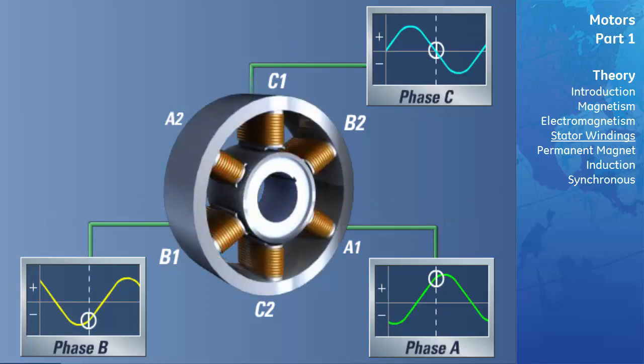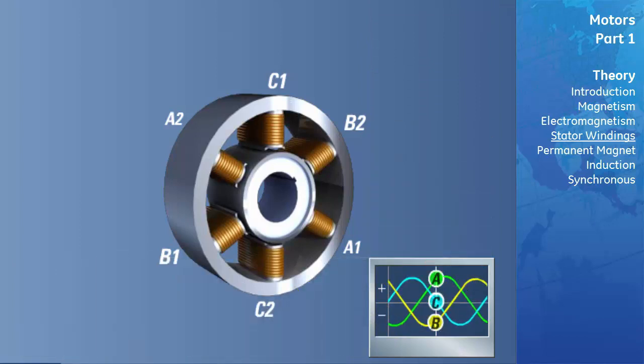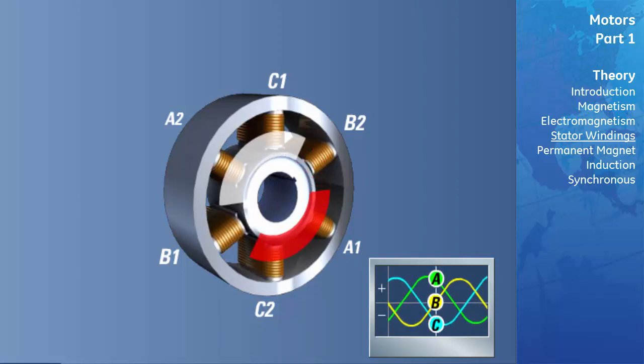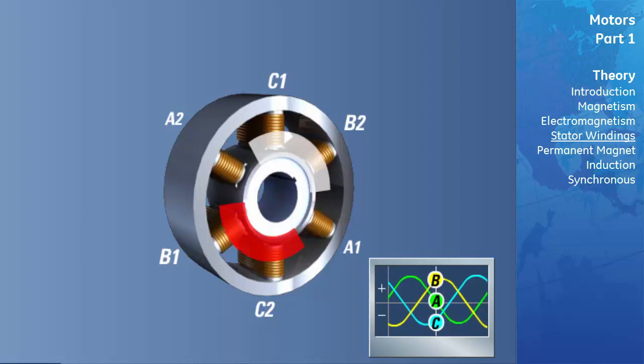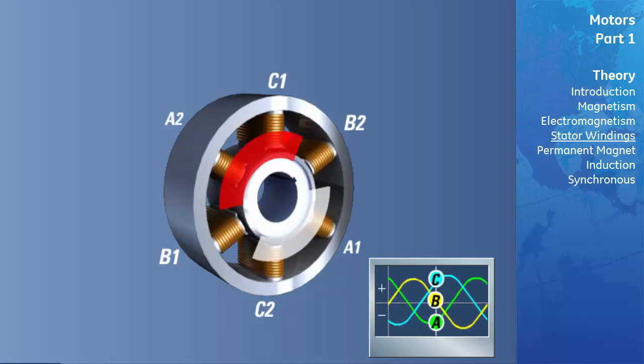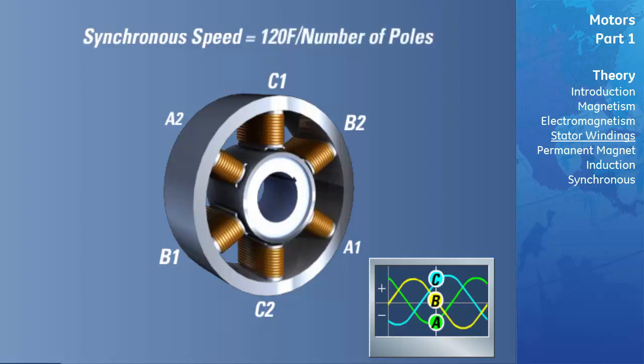If we compare the angular displacement of the field, we can see that it has rotated 60 degrees. If this evaluation is repeated every 60 degrees for the rest of phase A's cycle, we will see that the resultant stator field goes through one complete revolution, or 360 degrees. With a frequency of 60 hertz, this means in one second the field will go through 60 complete rotations, and in one minute, 3600 rotations. The speed of the rotating magnetic field is referred to as the synchronous speed, which can be calculated by the formula: synchronous speed equals 120 times the applied frequency divided by the number of poles. Applying this equation to a four-pole motor gives a synchronous speed of 1800 RPM.